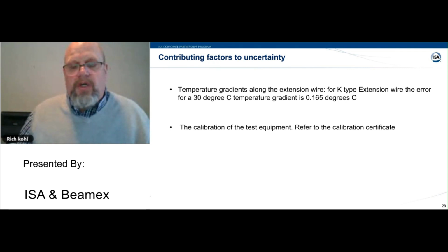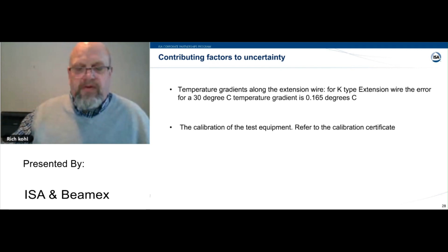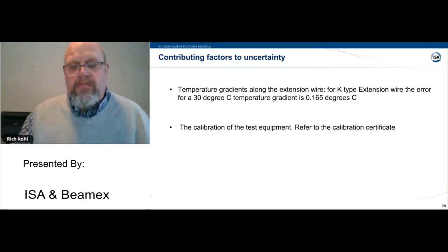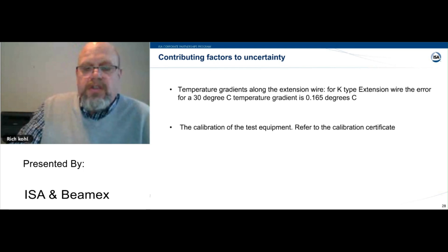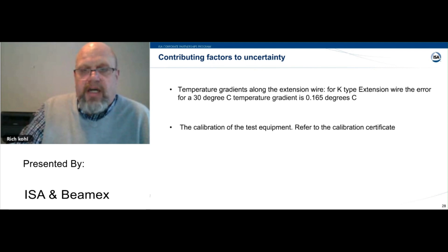We used to do a lot of calibrations in heat treat shops where we're working around furnaces, and a lot of times the hookup for the temperature sensor was in the back of the furnace where it was very hot, but our calibrator had to stay out in front where we could see it and manipulate it. So we had to use extension wire. We used that 30-degree gradient across that entire length of wire as a worst-case scenario. There are ASTM standards that will give you the exact amount of error per degree C of gradient across your extension wire. So this is just an interesting contributing factor.